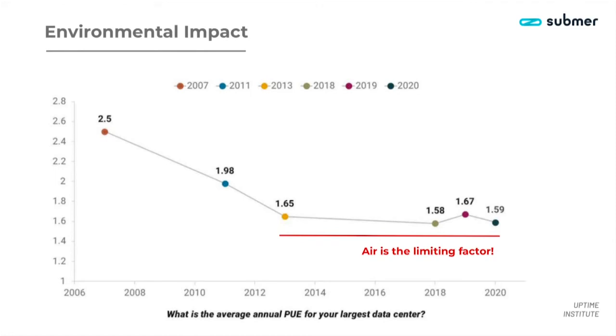And that, at the end of the day, we'll see now in a slide that I'm going to show, means we can use dry cooling infrastructure in the exterior of our data centers instead of chillers and compressors and evaporative type of cooling systems. So essentially, the energy footprint per kilowatt falls from the 1.6 that's being reported by the Uptime Institute down to 1.03.